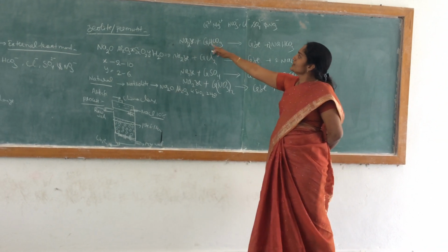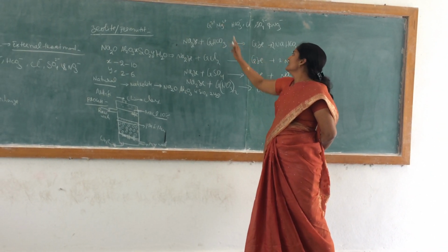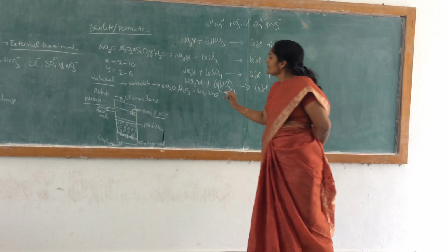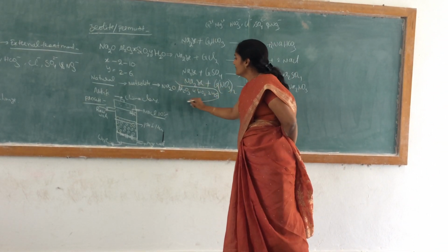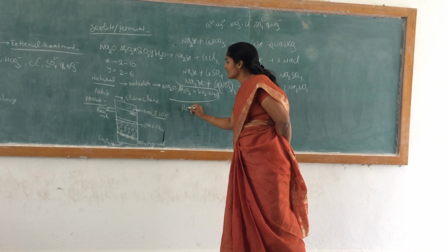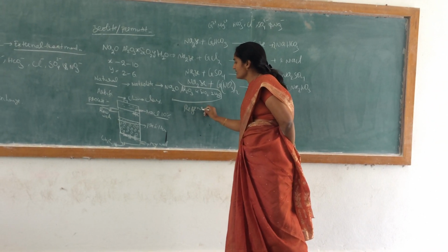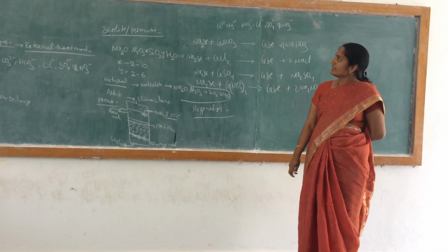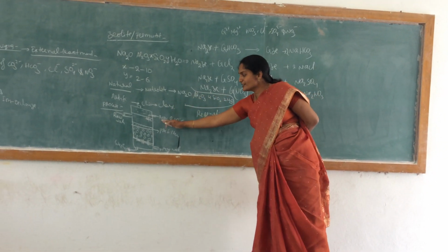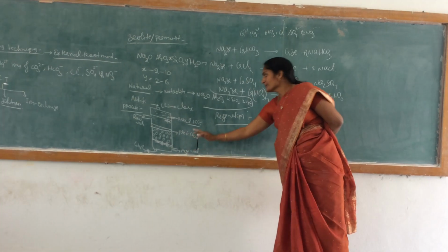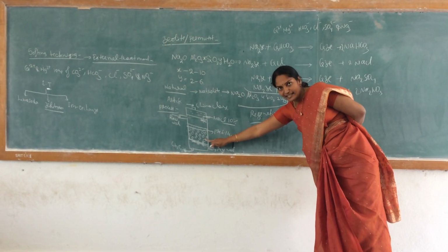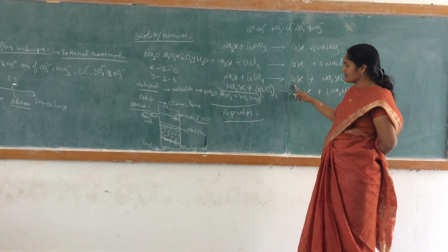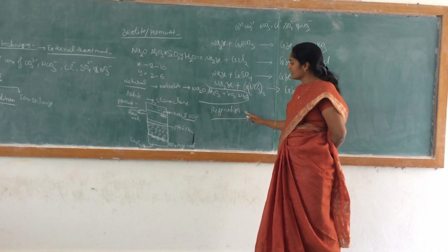Here the calcium and magnesium can also stick to the zeolite bed, and after completing the process we go for regeneration. After filtration for 6 to 8 months, the bed can be completely exhausted with calcium zeolite and magnesium zeolite. Then we go for regeneration.